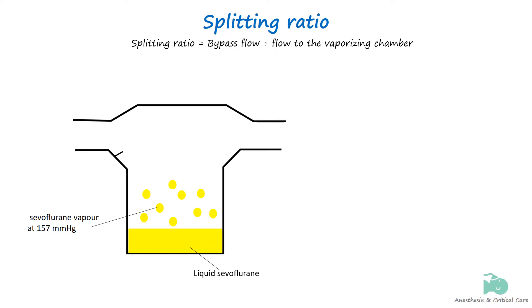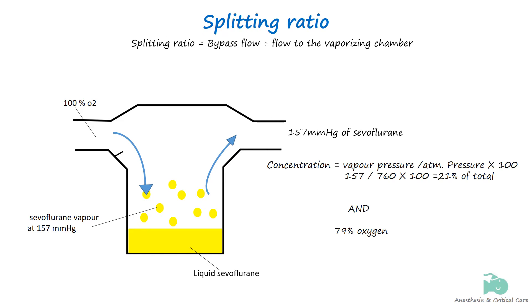The vapor covers the liquid sevoflurane. Now let's add a fresh gas or oxygen flow to get that anesthetic vapor. The resultant gas flow will now have the vapor of sevoflurane in it, assuming the flow is slow enough to let it equilibrate. This is 157 mmHg, or approximately 21 percent of total flow if expressed as a percentage.